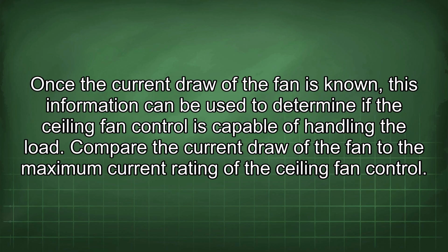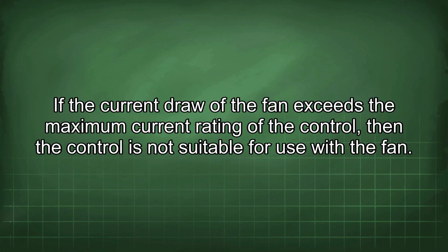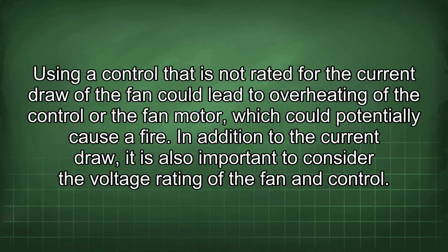Once the current draw of the fan is known, this information can be used to determine if the ceiling fan control is capable of handling the load. Compare the current draw of the fan to the maximum current rating of the ceiling fan control. If the current draw of the fan exceeds the maximum current rating of the control, then the control is not suitable for use with the fan. Using a control that is not rated for the current draw of the fan could lead to overheating of the control or the fan motor, which could potentially cause a fire.